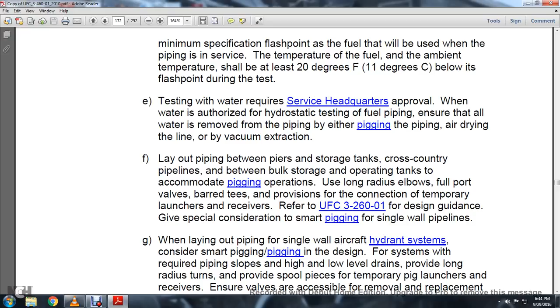When laying out pipeline for the single wall aircraft hydrant system, consider smart pigging and pigging in the design of the system, with the required piping slope and high and low level drains. Provide long radius turns, and provide spool pieces for the temporary pig launchers and receivers. Ensure the valve is accessible for the removal and replacement of the spool pieces.